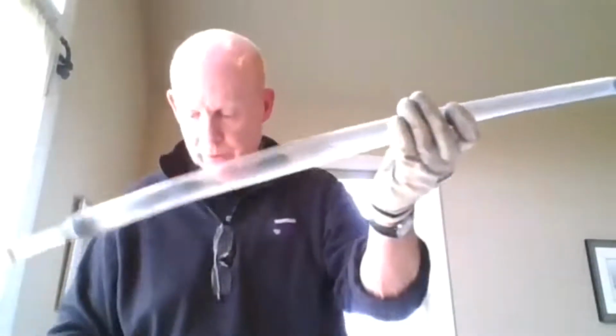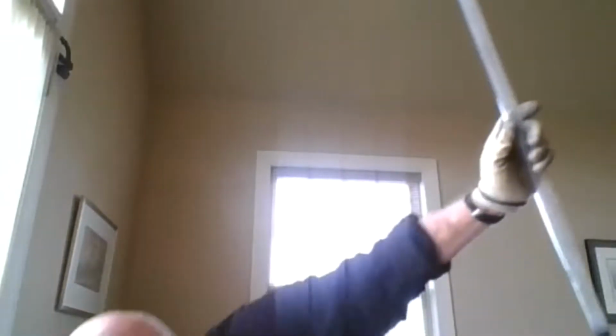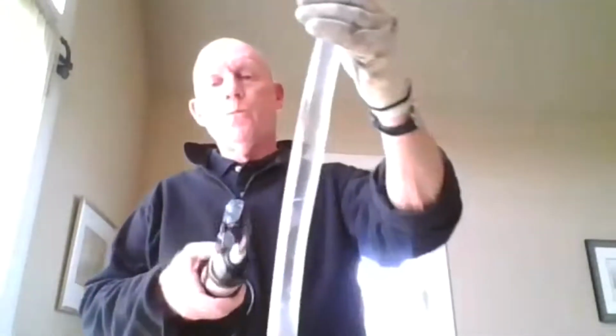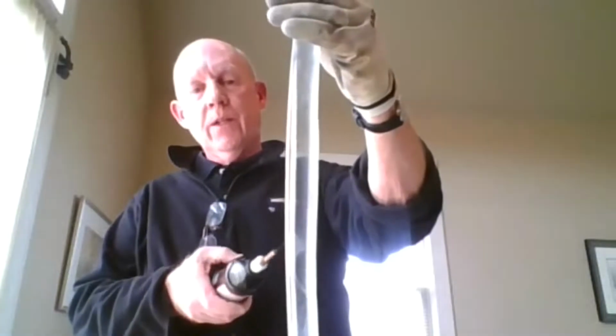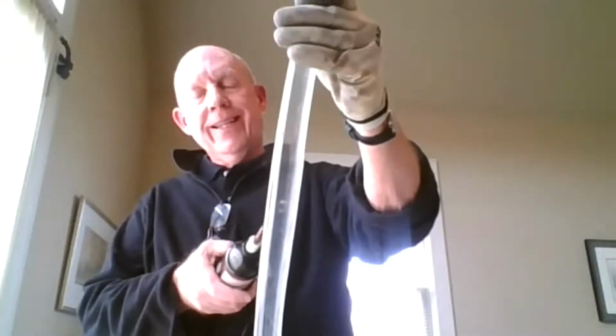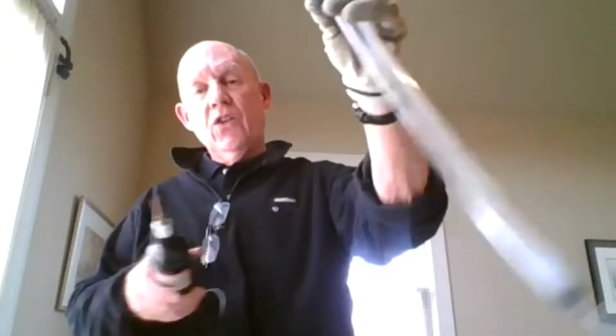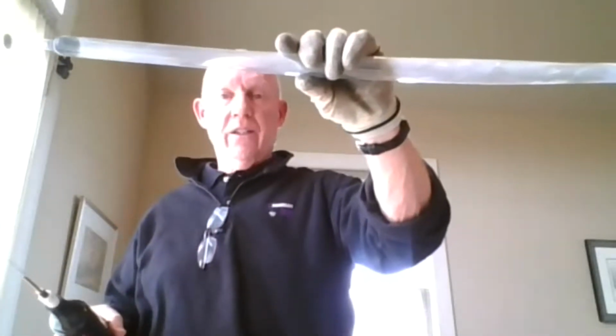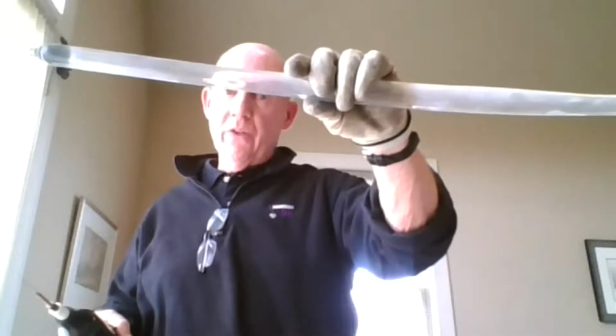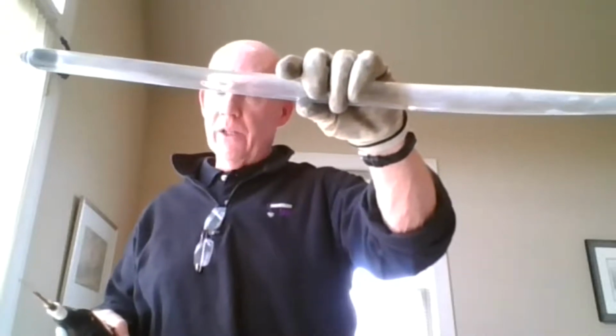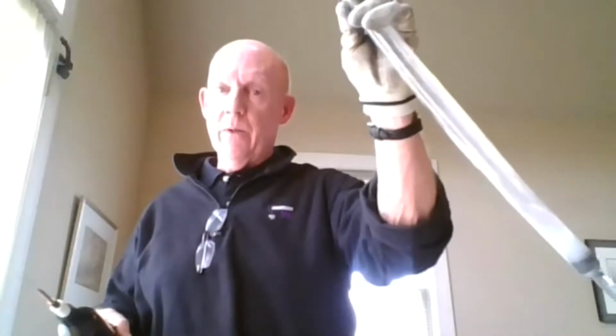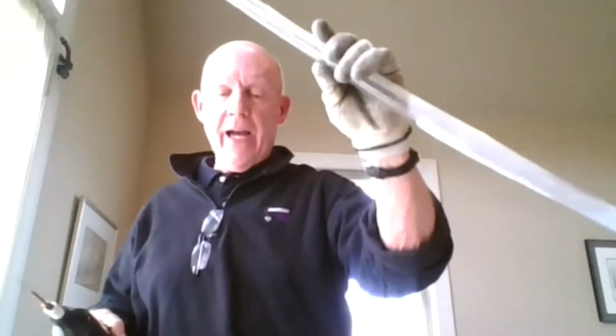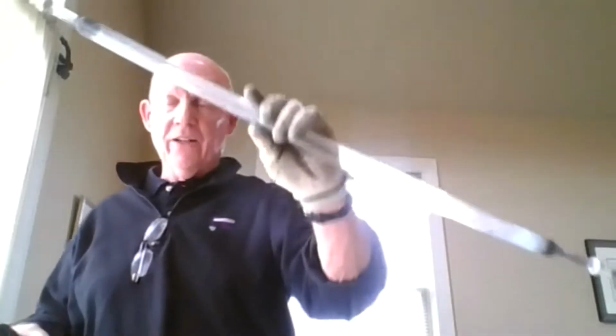Now, the scary part is, here's my bowed, deformed lamp. Uh-oh. It still fires. So if you're running to failure, this is what you could be using. It still lights, but you're not getting much UV light out of this lamp. So again, inspect your lamps, inspect the reflectors, know what's going on with the system.